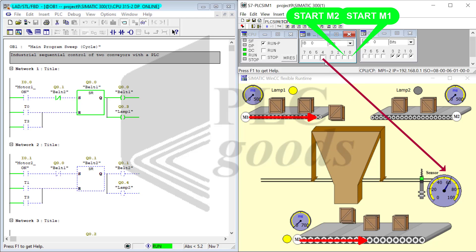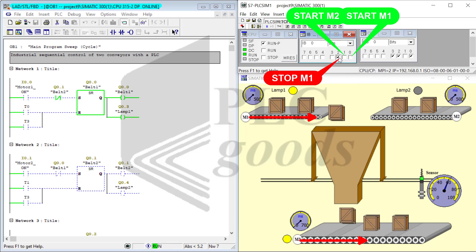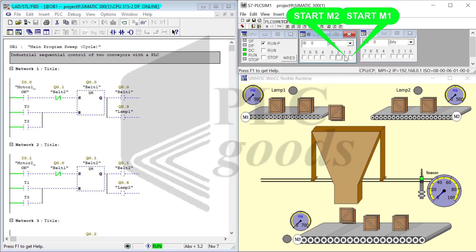Notice that tapping the I4 input resets the sensor timer, ensuring continuous measurement within the 10-second window. After pressing any related stop push button, M1 or M2 stops after 5 seconds and M3 after 7 seconds. The same logic applies to controlling the M2 conveyor motor as well.